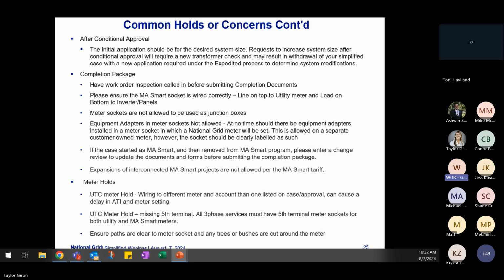For Mass Smart, ensure that your Mass Smart socket is wired correctly, line on top, load on the bottom. Meter sockets are not allowed to be used as junction boxes, as JJ mentioned earlier, and equipment adapters are not allowed.